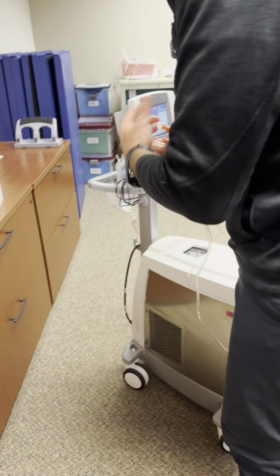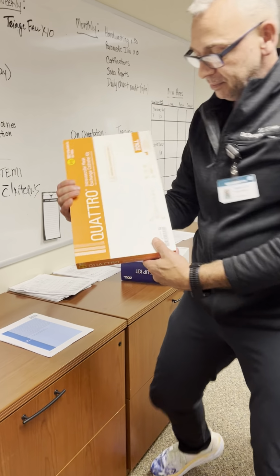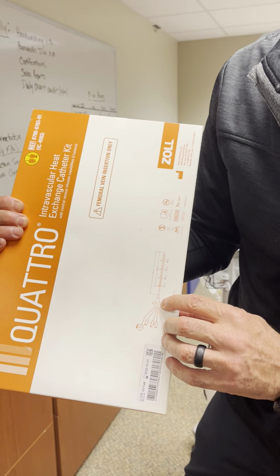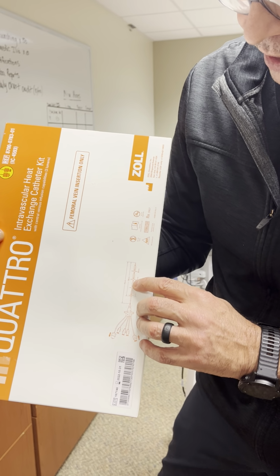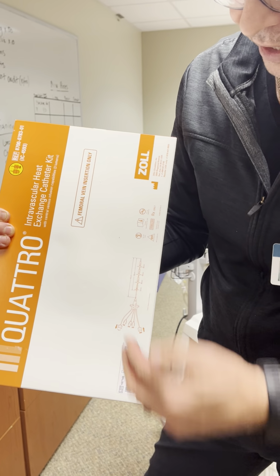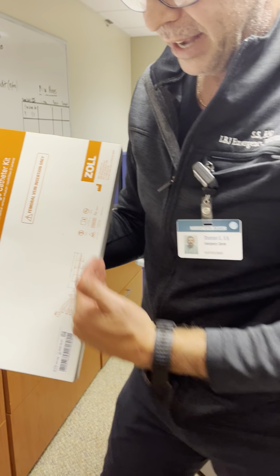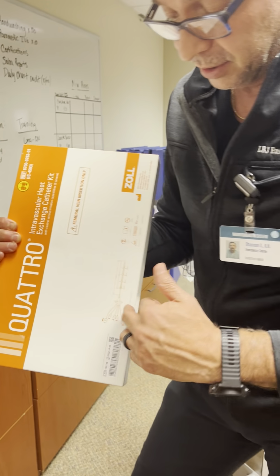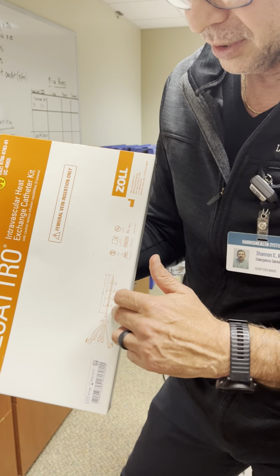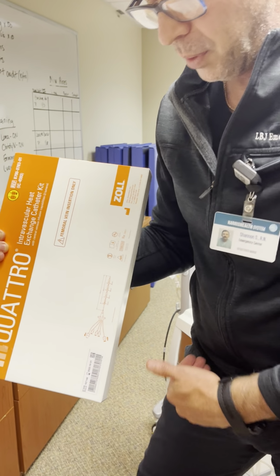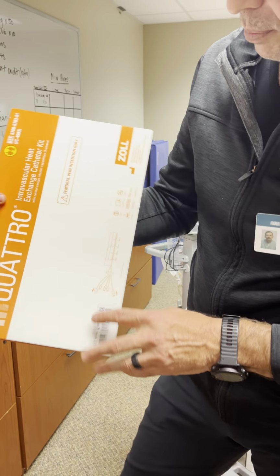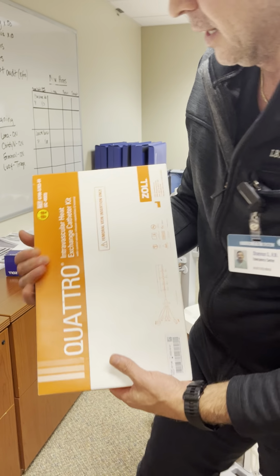The way that this system works is, given your set point, whether you're heating or cooling, the saline is going through this catheter into these 4 balloons and then coming back out again. That way it continually has the same set point of temperature on the saline that's going into the catheter. The blood going by the femoral vein, because that's where we put these catheters, is cooled.